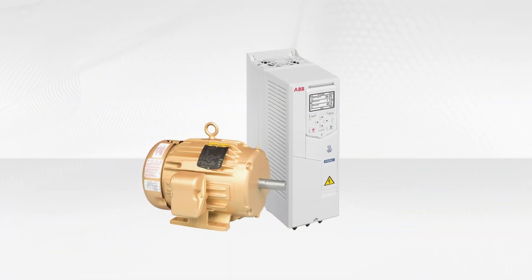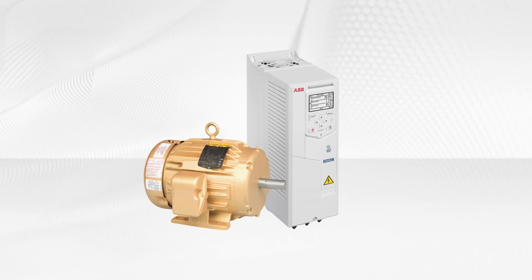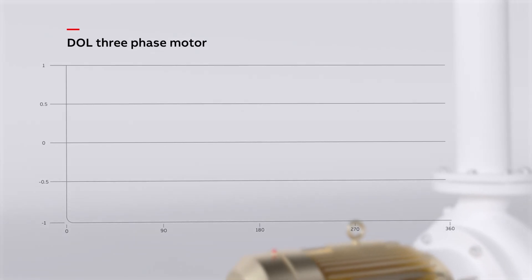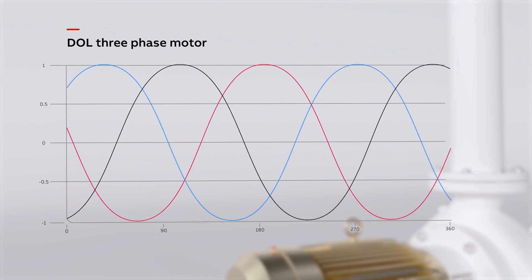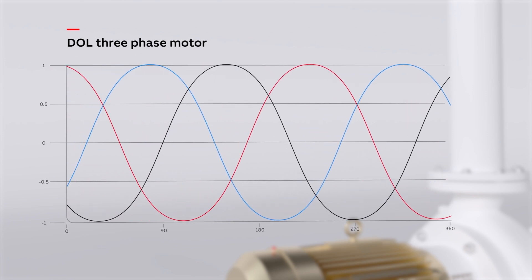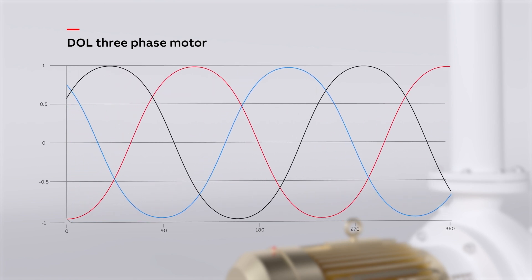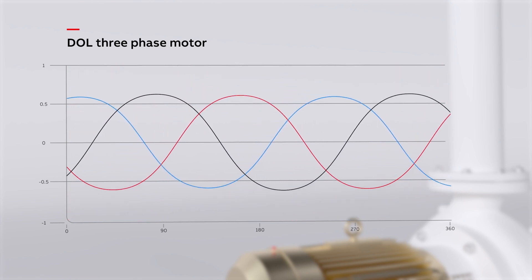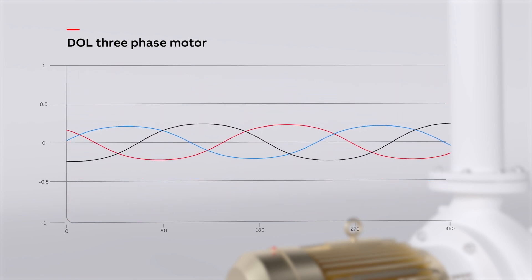Let's look at the difference between a direct-on-line motor versus an inverter-driven motor run with a VFD. When using a direct-on-line motor, the three-phase wave power is balanced in frequency, phase, and amplitude. When properly balanced, the vector sum of the three phases equals zero volts.